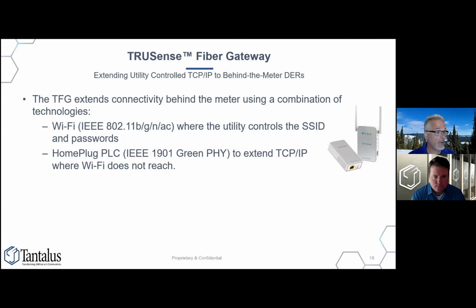The other element is home plug PLC, because maybe the TRUSense Fiber Gateway is installed at or near the transformer, and the Wi-Fi isn't going to reach into the basement of the premise where the smart hot water heater is. So you use these devices, which you've probably seen in your Best Buy catalog, that convert from wired Ethernet or Wi-Fi to the home plug standard. We use the GreenPHY substandard of the IEEE 1901 standard, which is slower but gives greater reach, so you can connect to all the behind-the-meter distributed energy resource devices.